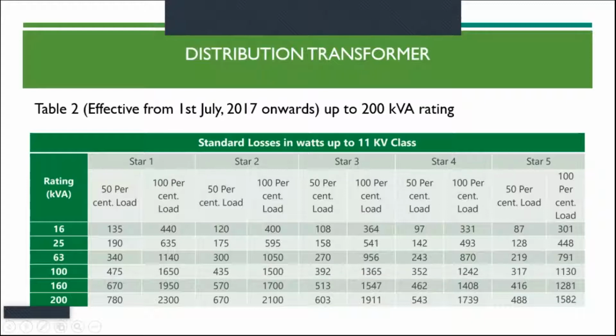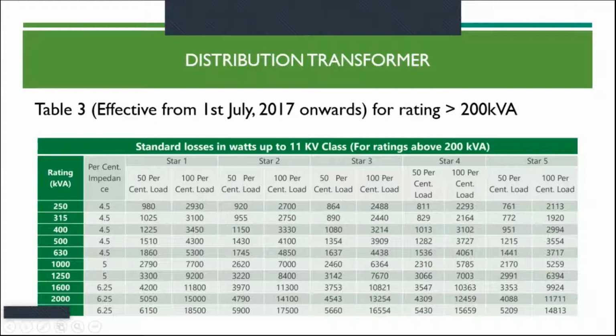You can see here 16 kVA distribution transformers at 50% loading in the 135 to 440 range. Then the Government of Punjab has revised the mandatory usage of distribution transformers to 2-star. Now 2-star is mandatory in the state of Punjab, and if we use a 200 kVA distribution transformer, then the losses should be 670 at 50% load and 2,100 at 100% load. You can say these are the standard losses. Now the range has also increased from 200 to 2,500 kVA transformers.